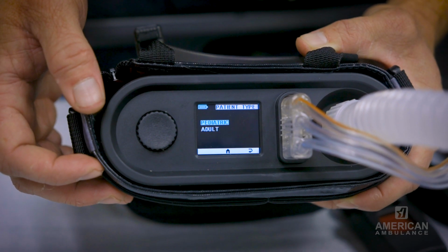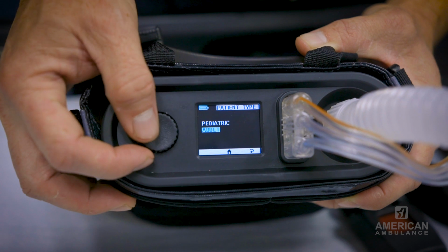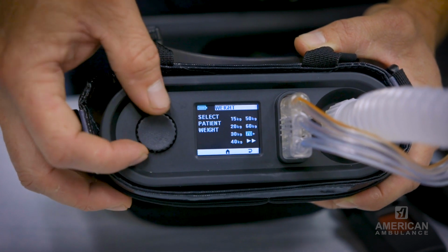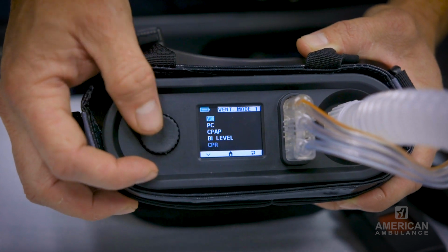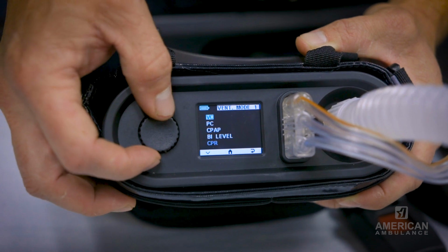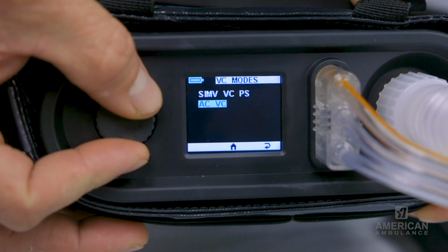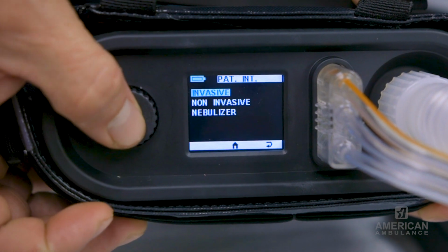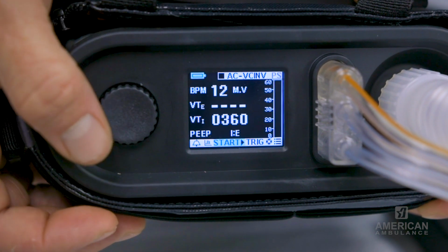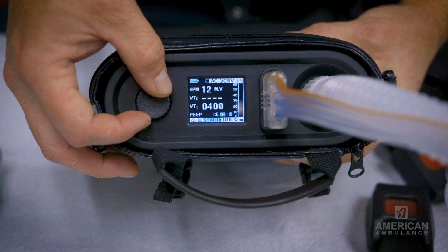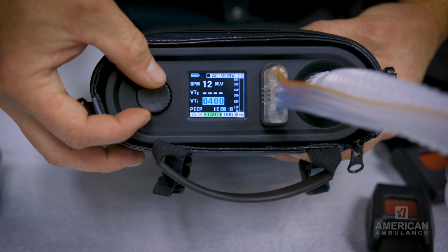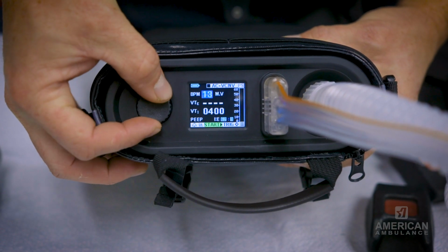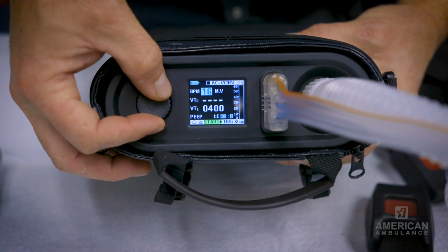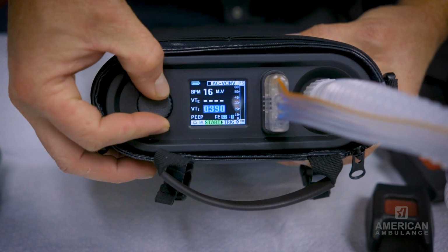After completing the circuit test, select either adult or pediatric, select the patient's ideal body weight, and select the proper ventilation mode. After the initial setup, change the ventilator settings to match the hospital settings. Change the breaths per minute to 16 and the tidal volume to 350.